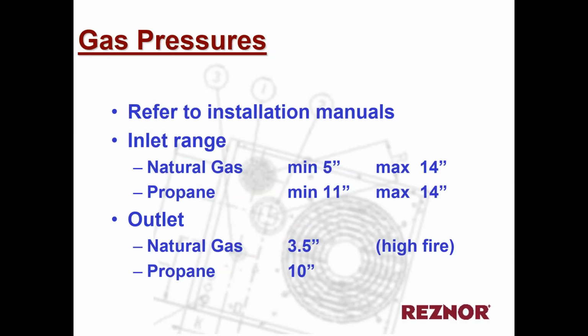Once again, for most of our product, you have to refer to the installation manuals before installing. But as far as where we stand gas firing wise, our inlet range for most of our product on natural gas is from 5-inch minimum to 14-inch maximum on the gas pressure inlet range. Propane is 11 inches to 14 inches, a little narrower window, but it's good to know. Outlet, the burner side would be 3.5 inches, and on propane it would be 10 inches. So we would need those inlet pressure ranges to guarantee those outlet gas pressure ranges on either natural gas or propane.